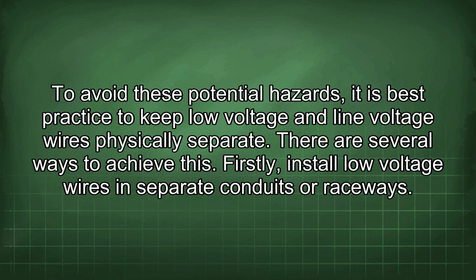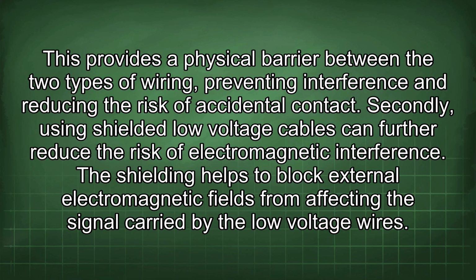There are several ways to achieve this. Firstly, install low voltage wires in separate conduits or raceways. This provides a physical barrier between the two types of wiring, preventing interference and reducing the risk of accidental contacts. Secondly, using shielded low-voltage cables can further reduce the risk of electromagnetic interference. The shielding helps to block external electromagnetic fields from affecting the signal carried by the low-voltage wires.